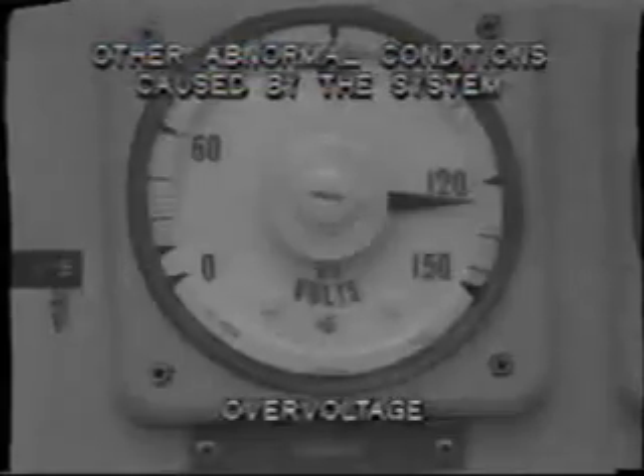Yet another internal fault could cause the failure of excitation altogether. This could provide a serious upset to the power system as it attempts to supply the excitation current through the stator windings. We'll be talking about this and other faults in more detail later in this tape. Other possible abnormalities may be due to system conditions such as excessive stator current. This results in overheating of the stator windings, overvoltage, which may damage insulation, underfrequency, which may damage the turbine blades due to vibration, motoring of the generator due to loss of the prime mover. This could result in overheating and consequent damage of the low-pressure turbine blades.